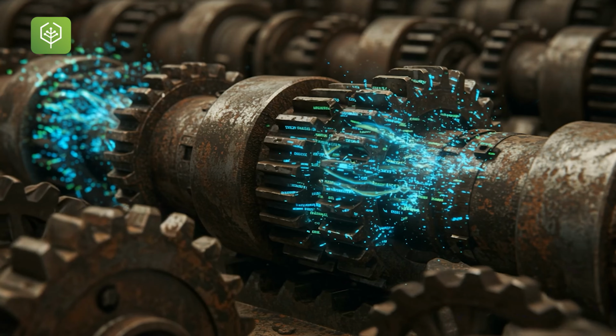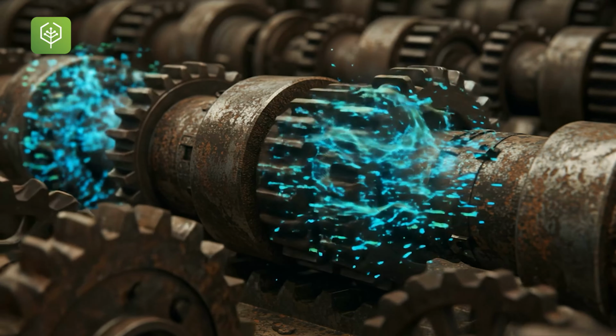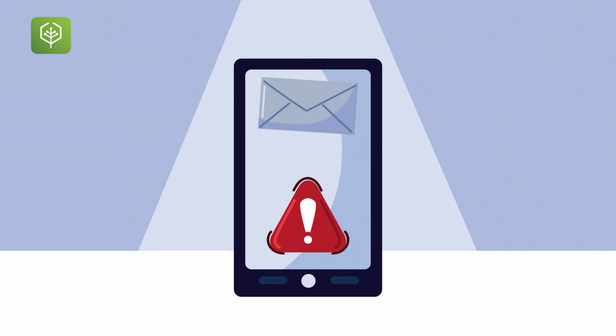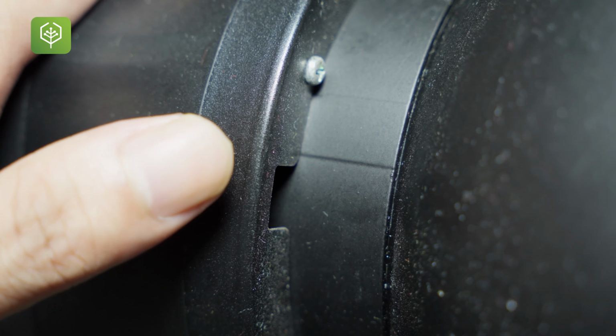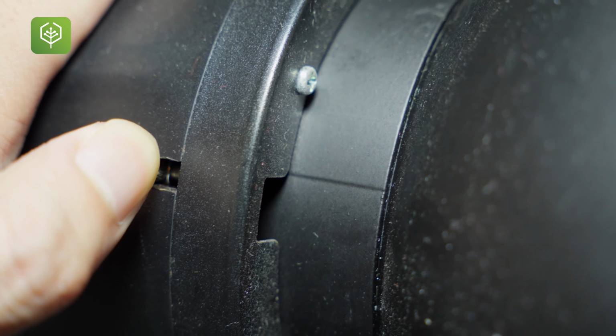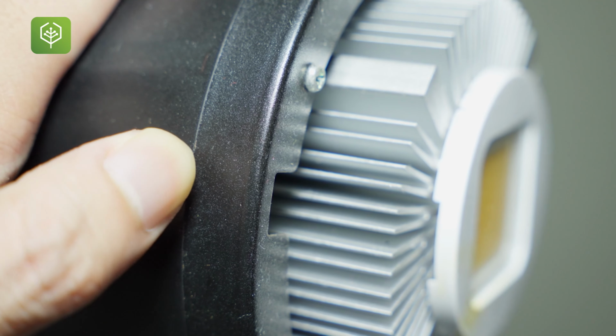the drive system. So if your motor is consuming more current, you can get the data, you can process the data, and if something is really fishy, the alerts can be triggered, and you can get notified whether your motor is in overload conditions. In the same way, if the surface temperature of the motor is increasing, you can get to know whether the operating conditions are getting worse. And in the same way, you can also add on additional vibration sensors to monitor the VRMS, ARMS values for the specific motor vibration systems.